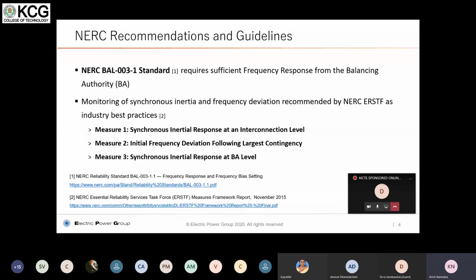So balancing authority levels are nothing but, inside India, very similarly, areas where you have enough generation and load, and you can basically balance area-wise, where you generate some megawatts and you also have the loads that need to be balanced out. So they can be classified as each area basically. In India, basically the southern region, the northern region, the eastern region, these are all regions. Inside that, they will have a capability to balance load and generation basically.